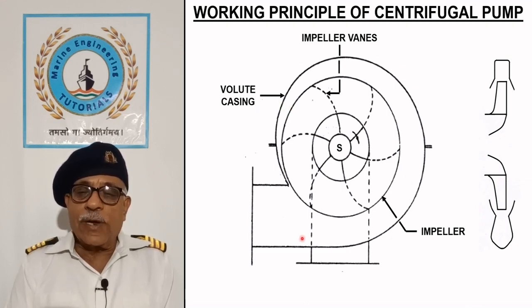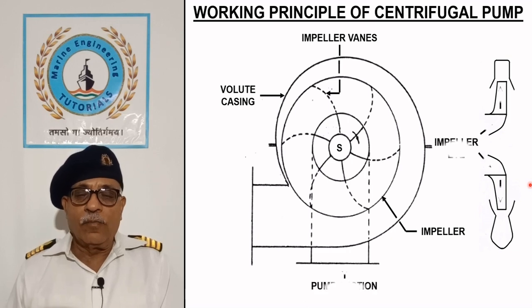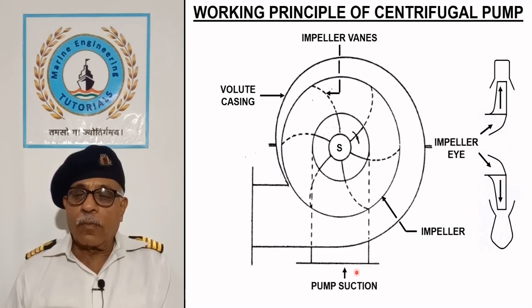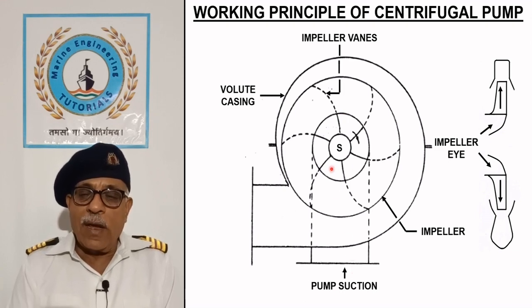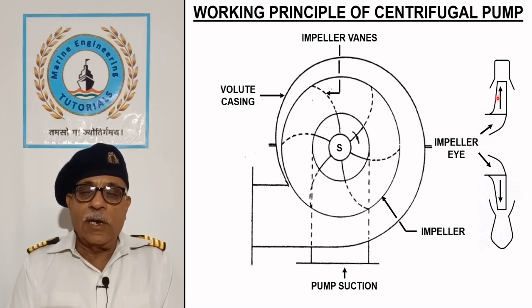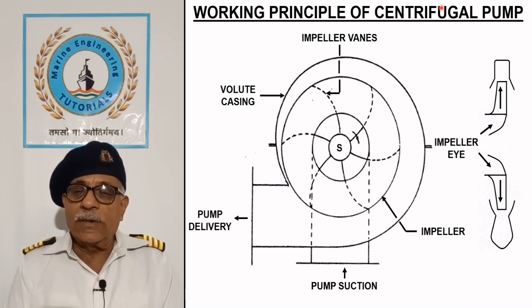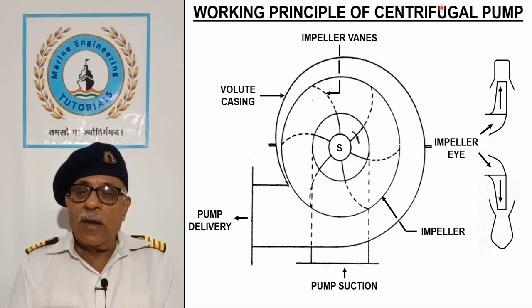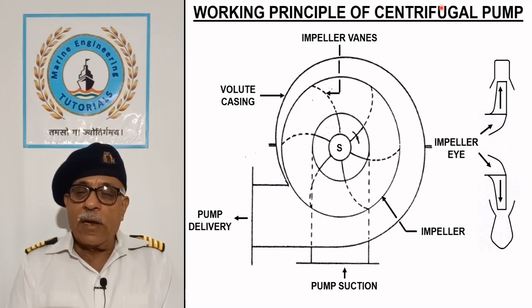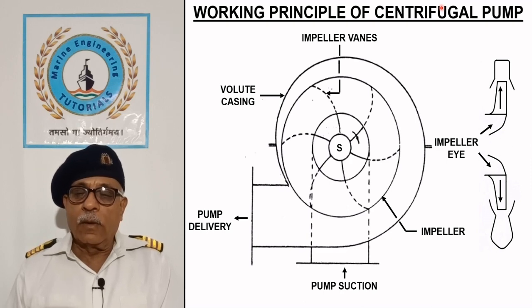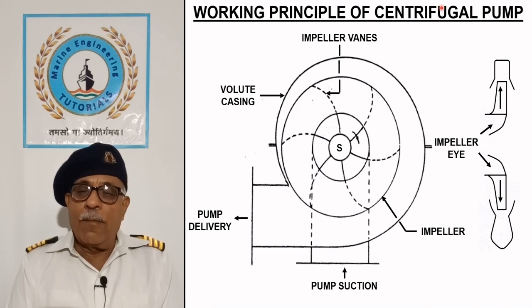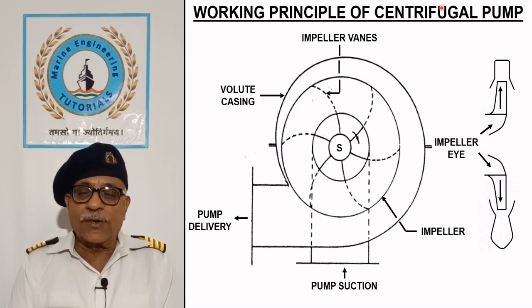The impeller rotates in a volute casing which converts the kinetic energy of the liquid into pressure energy. Liquid enters the impeller eye from the inlet connection axially and is delivered to the volute casing radially. As the liquid is thrown out, a vacuum is created at the eye of the impeller and more liquid is induced to fill up the space. Once liquid reaches the eye, pumping starts and it continues as long as the required net positive suction head is available.